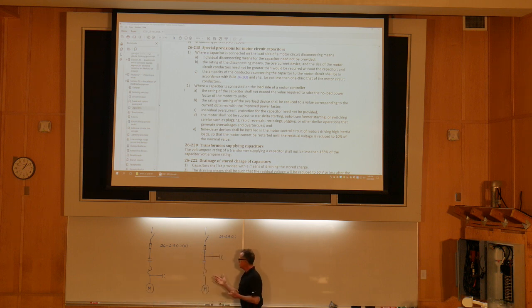So when we do power factor correction with a capacitor on a motor branch circuit like this, we're reducing the current. All right? The capacitor and the inductor, which is the motor, just start juggling current back and forth. So in this case, we've got a reduction of the line current here, and the capacitor and the motor are simply juggling current back and forth here, but it's all going through the overload. Here, when I have the capacitor connected up on the load side of the overload, we get a reduction of current through the overload. So we have to downsize the overload here, all right? But we have to read on because there's some unique things about this method that we've got to be aware of.